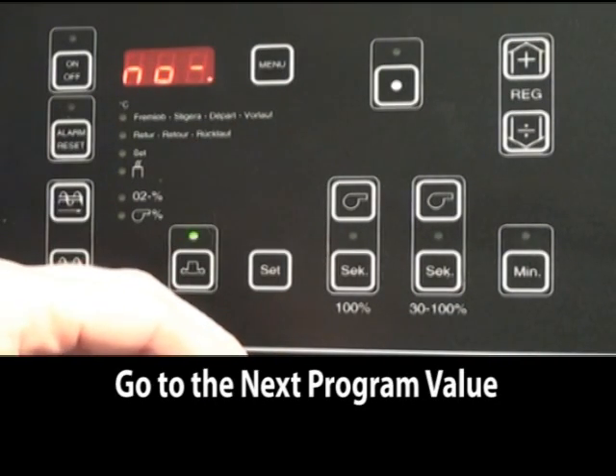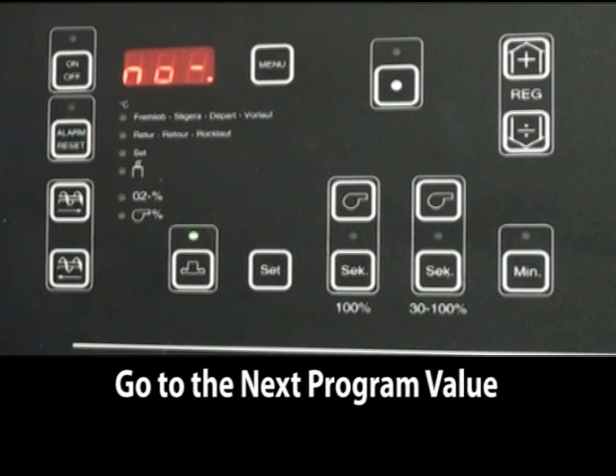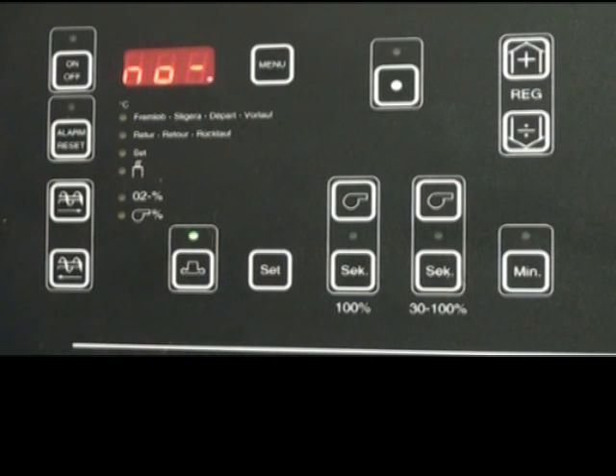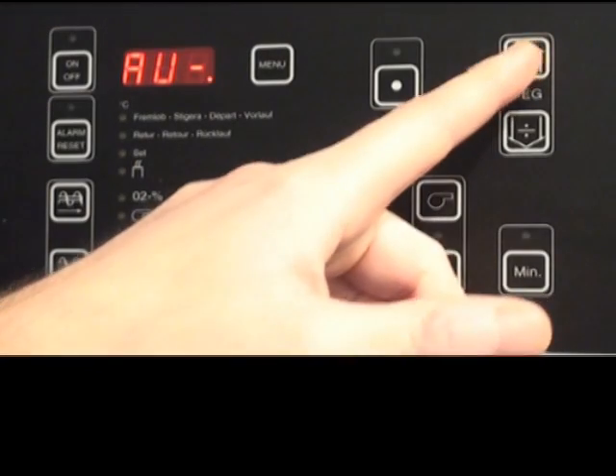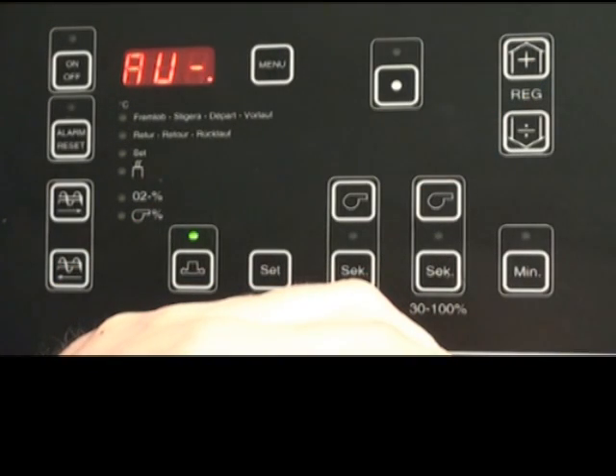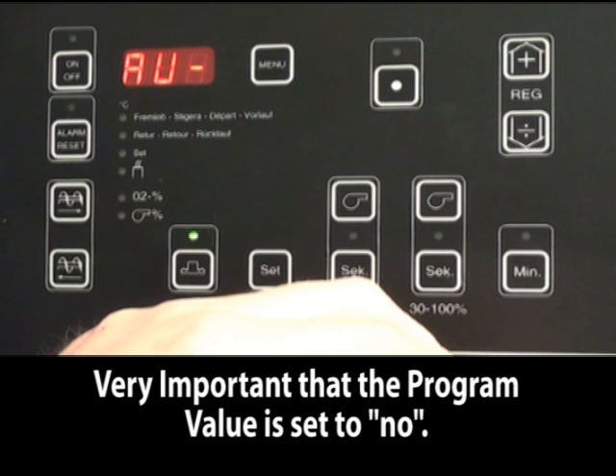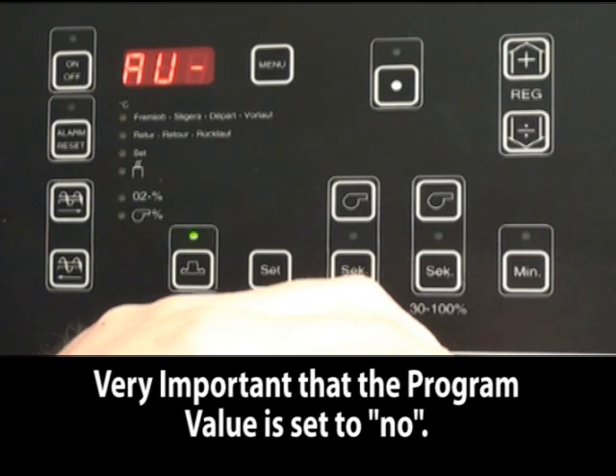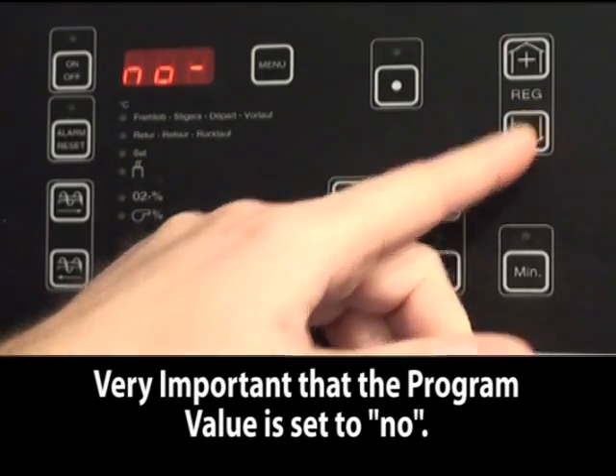The next menu should say no, or basically this is for the North American market. If it says AU, it must be changed to no. This is very important. The boiler will not run properly in the European mode, so make sure you do change it to no.